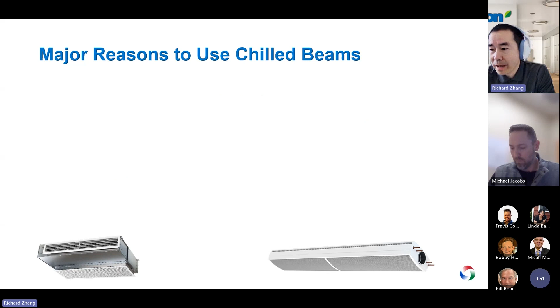Coming back to the other benefits of chilled beams over other equipment - they significantly reduce refrigerant use. It may not be a big deal when we're using R410, which is A1, not toxic, not flammable, so that's not a big deal. But you have to bear in mind, when you switch over to A2L, it's flammable, so any reduction of refrigerant can be a benefit, especially against the VRF system.